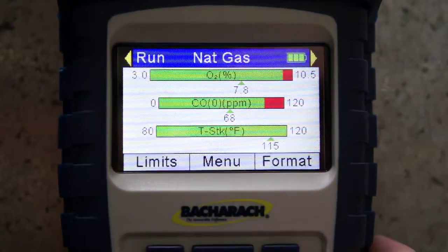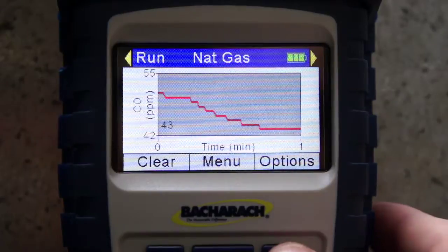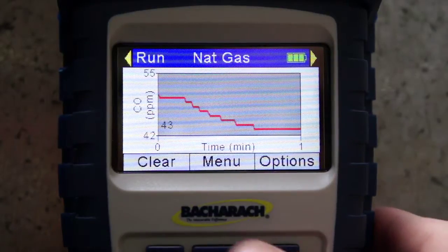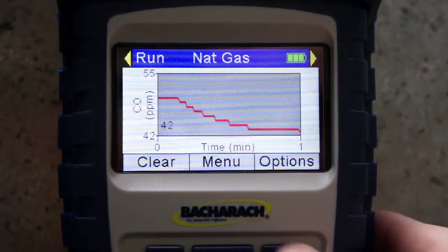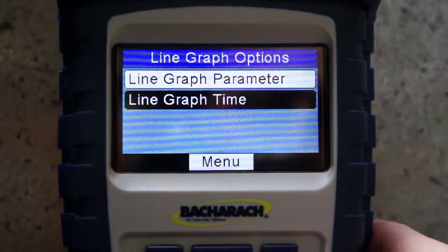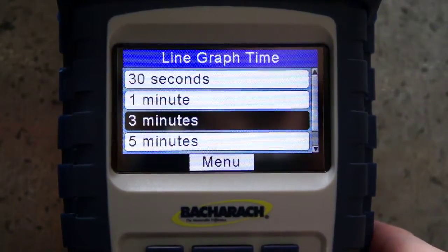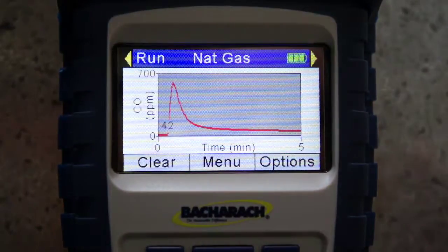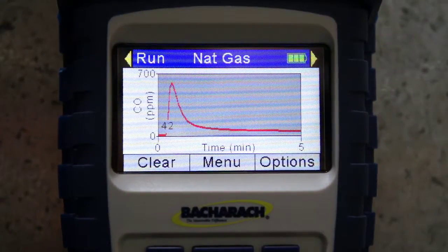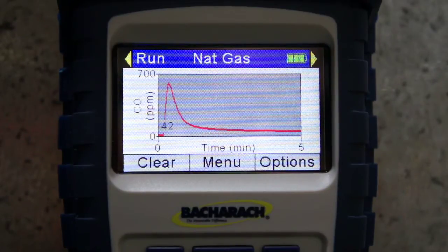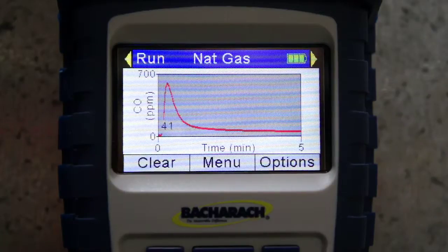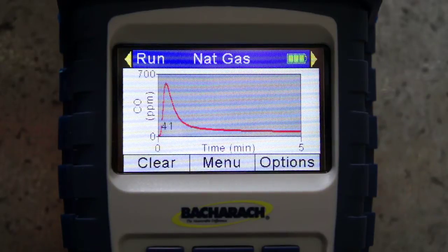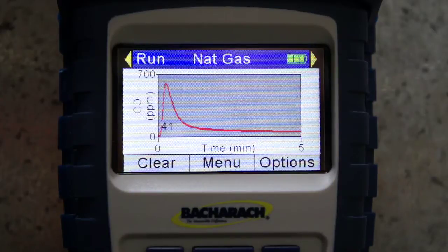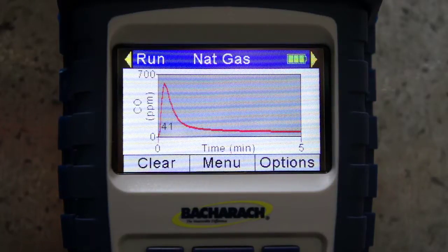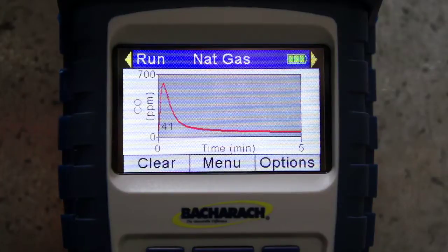I can also scroll back here now, and I can look at my CO trend and CO air free trend, and I'm going to go ahead and change this again to a little bit longer of a time here. Line graph. I'm going to take this out to, let's say, 5 minutes. Hit enter, and I can see that my CO was trending downward the entire time I'm doing my test. So now I can make sure that several things are exactly the way I want them. CO, although it had a little rough light off, is trending downward, and CO is not changing the entire time I'm doing my testing. That's exactly what I want to see, a nice smooth transition on the CO line.